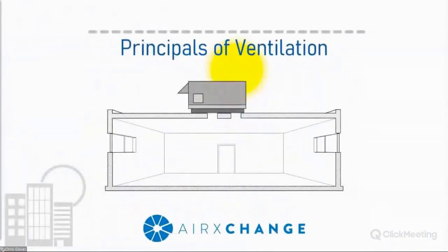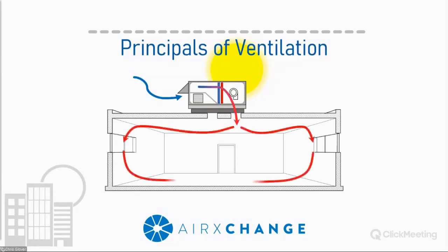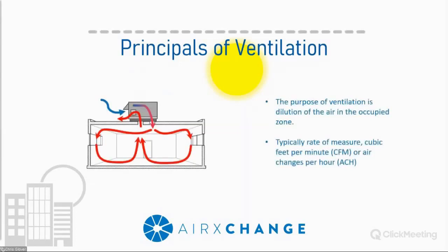Okay, so let's take a look at a typical ventilation process. The outside air comes into the HVAC unit. That air is then conditioned to a point where it's acceptable to be delivered into the space. That fresh air then dilutes the stale space air, which is displaced and exhausted outside the building. So the benefit of ventilation is dilution. Dilution in its very basic form is the continual reduction of concentrations of contaminants of concern.